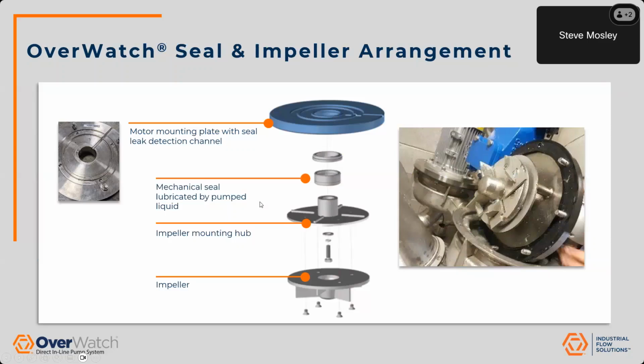The motor is mounted to a mounting plate which has a seal leak detection channel. That channel will weep any leakage off to the side away from the system itself. So the motor is still protected and dry in that situation, and it does indicate a leak. We do offer the option to put a leak detector in that channel that would alert the control panel if you do happen to have a leak. Mechanical seals that we use as standard are tungsten carbide, extremely hard faces, suitable for some pretty heavy duty installations. And as we continue going down, the impeller mounting hub is what holds the mechanical seal in place and is mounted to the motor shaft with a single bolt and is keyed in place so it can't slip.